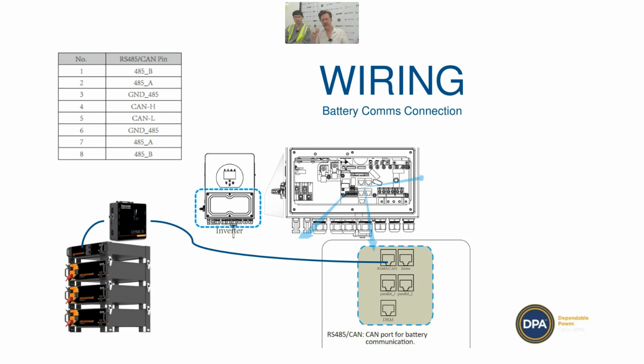These are mostly a straight through cable. And what I mean by that is it's not a crossover cable like you might see with Selectronic or Victron, where it's going to be on pins 1 and 2 at the inverter end and 4 and 5 on the battery end. They're mostly going to be a straight through cable, which makes things easier. So you can use a standard RJ45 cable.